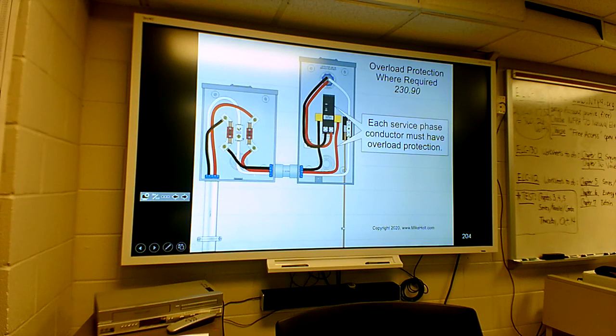This is where your meter base plugs into those sockets right there. So this is what it looks like if you take that round meter base off, you unplug it from the box. That's what it looks like behind it, with those quick connect female stabs in there. Those of you that are doing residential, how many of you are working on that right now? In that room, if you go all the way to the right, all the way to the back, I think the trainer on the left at the very back end, you might not even be working with it. That trainer has a meter base on it. It's got the glass meter base with the wheel. If you go back there, you can pull that thing out. Grab hold of it with both hands, wiggle that meter base, the glass part, and pull it straight out, and you can see it's going to look like that behind on the left. It actually plugs into a quick connect with those copper bars in there. If you never took one off, you can go out there and try it and see what it looks like.